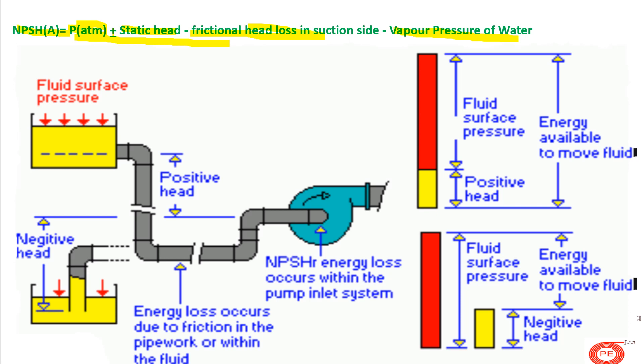With this sketch, let me explain the different terms. For static head — positive and negative: if the pump has positive suction, where water flows by gravity down to the pump centerline, we have a positive static head. But if the baseline of the tank is below the pump centerline and the pump must work against gravity, the static head becomes negative. Depending on the location of your tank, make sure whether your static head is positive or negative.